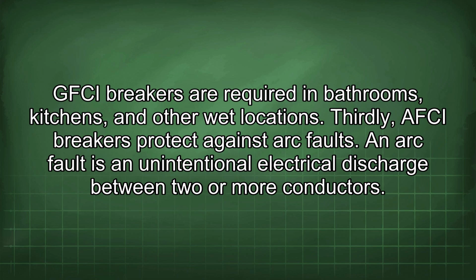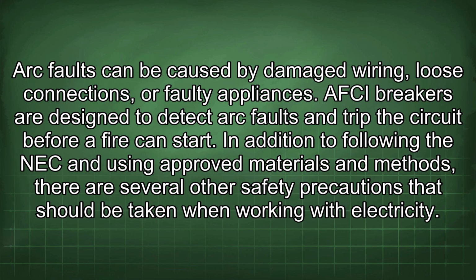Thirdly, AFCI breakers protect against arc faults. An arc fault is an unintentional electrical discharge between two or more conductors. Arc faults can be caused by damaged wiring, loose connections, or faulty appliances. AFCI breakers are designed to detect arc faults and trip the circuit before a fire can start.